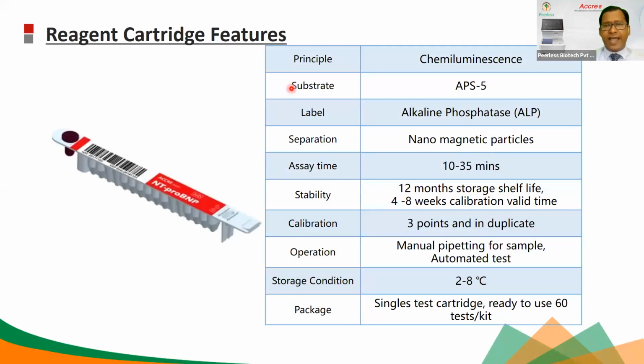So the reagent cartridge features, as I said: it is chemiluminescence, and alkaline phosphatase and the APS5 substrate are there. Nanomagnetic particles are there for separation. Assay time is 10 minutes to 40 minutes. It's not 35-40 minutes for vitamin D. The stability is 12 months storage life, and shelf life for some parameters is 18 months also, for many parameters. Calibration validity time is 4 to 8 weeks, and 3-point calibration is requested, which can be done in duplicate. And manual pipetting for the sample. Only the manual part is that you have to mix the sample in the cartridge.